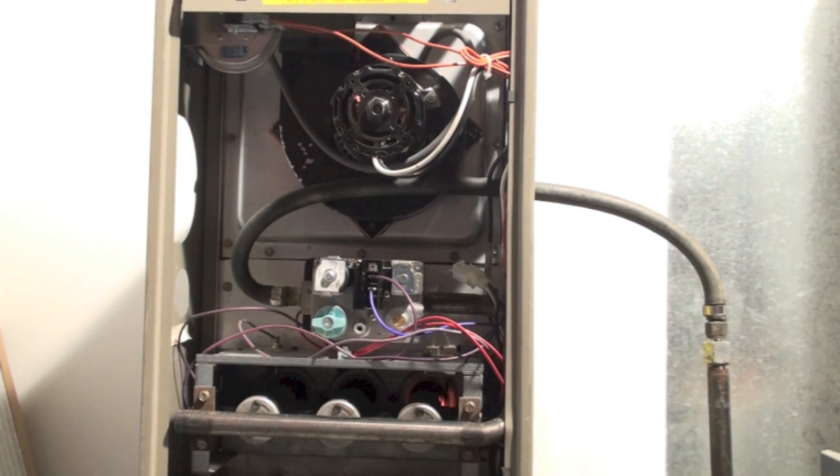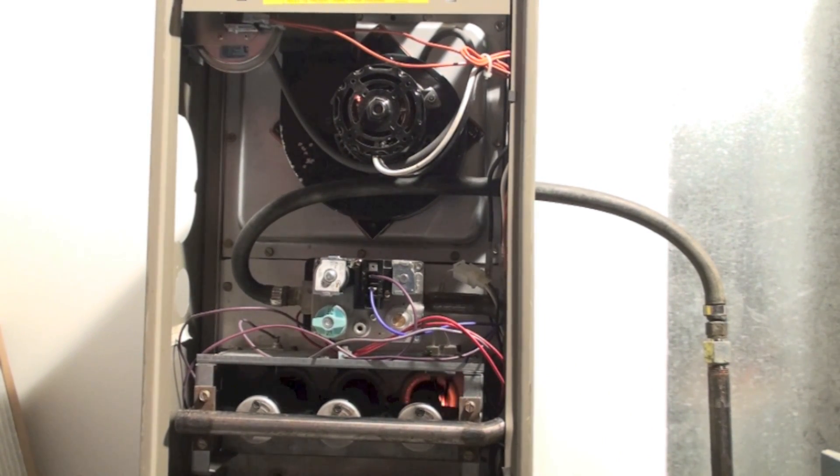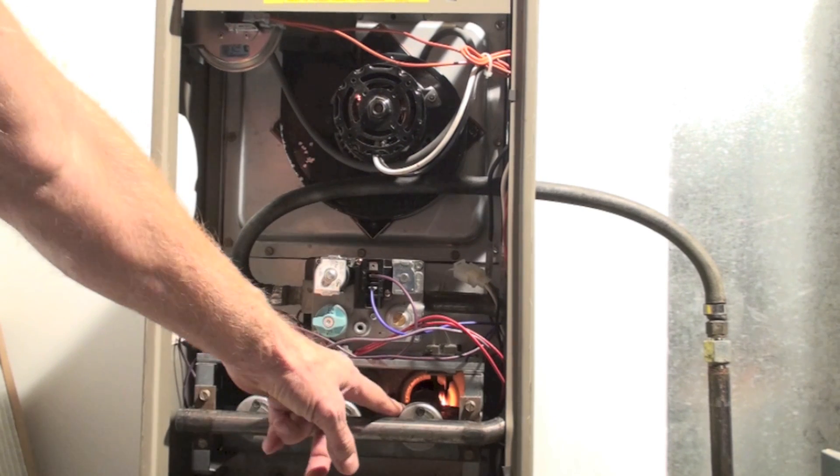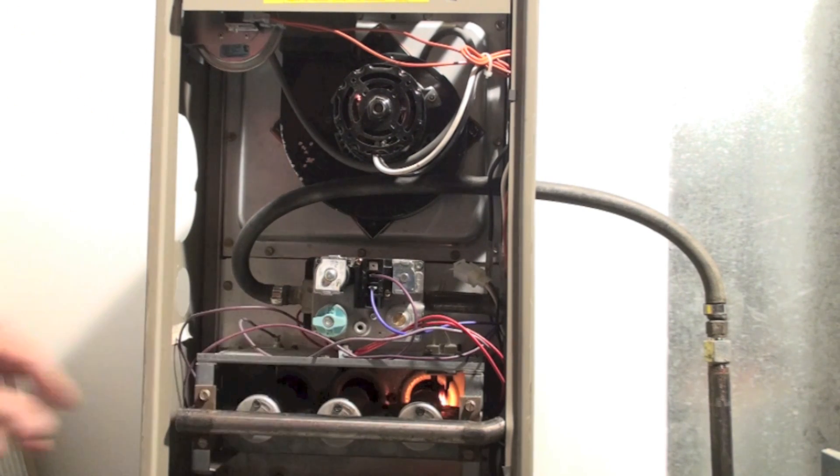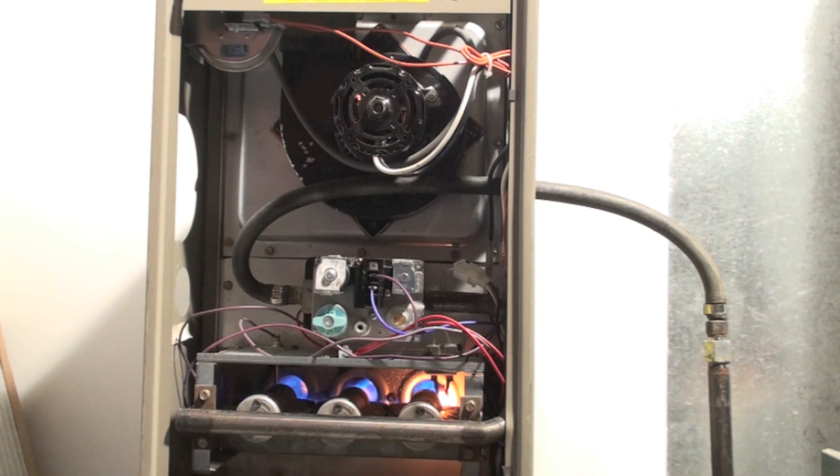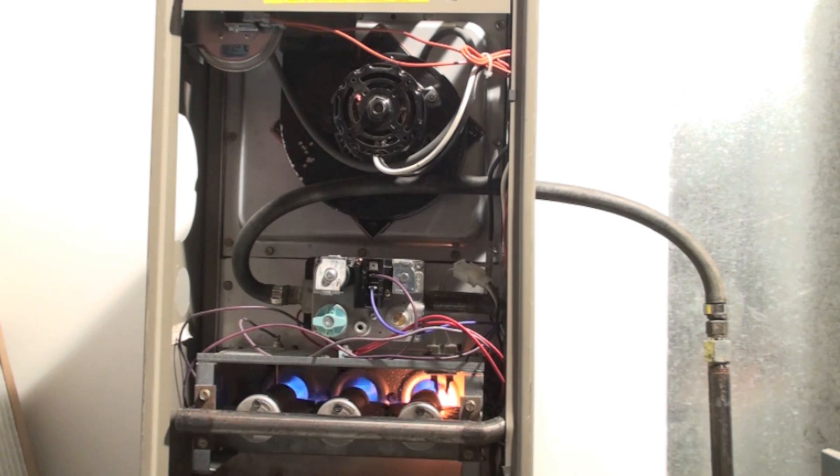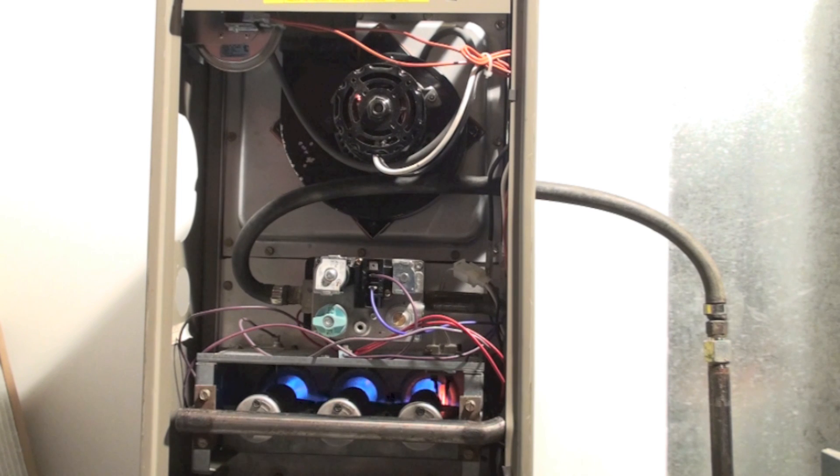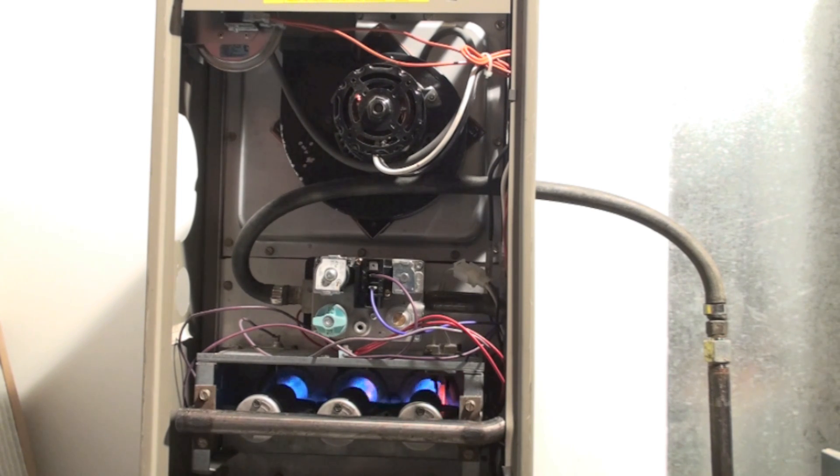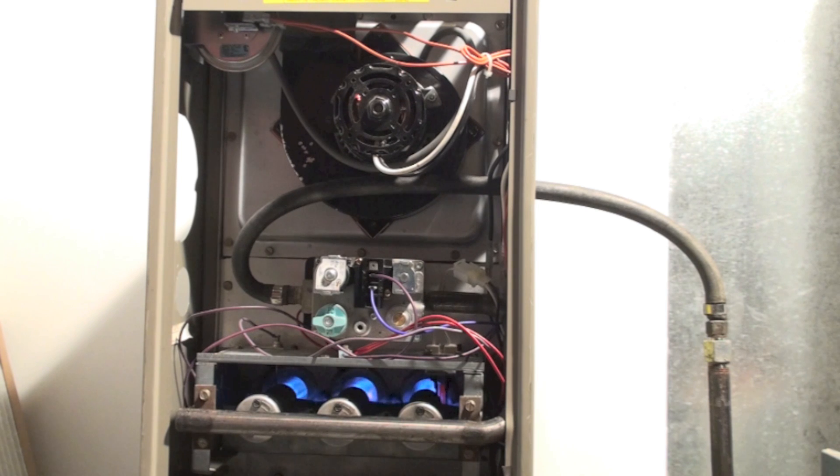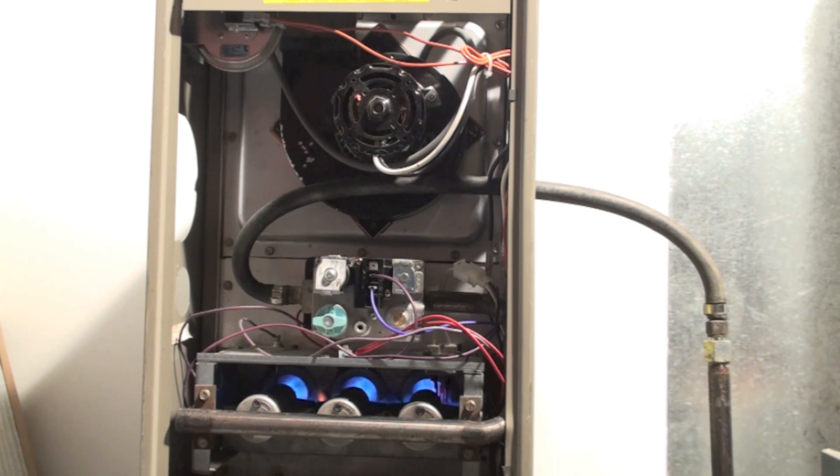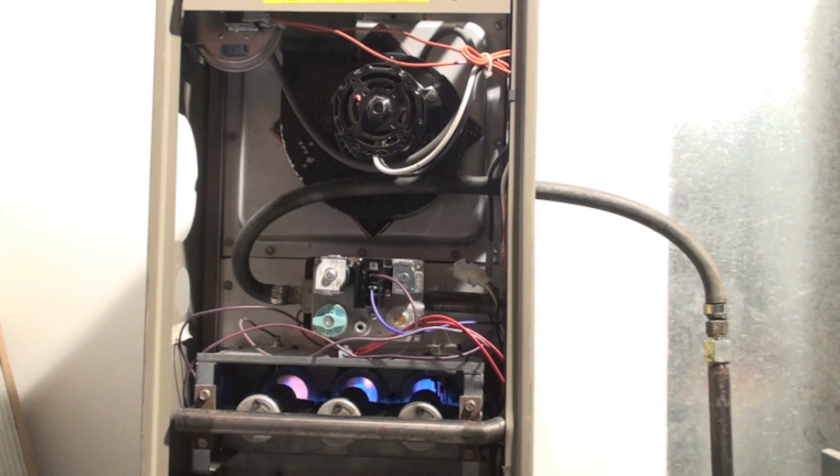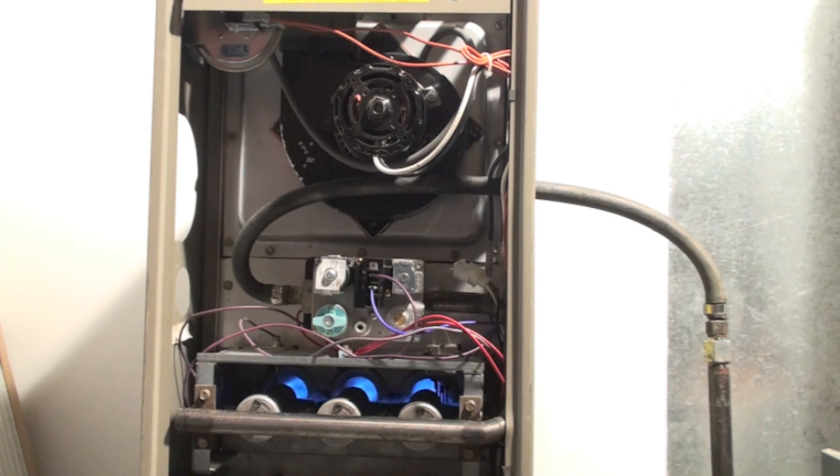Now you can barely see that little glow right over there. That's a hot surface igniter. Did you notice those burners? One lit, and then there was a hesitation and the others lit. That's not real good. Possibility there's a flame spreader problem where the flame is not passing from one burner to the other.